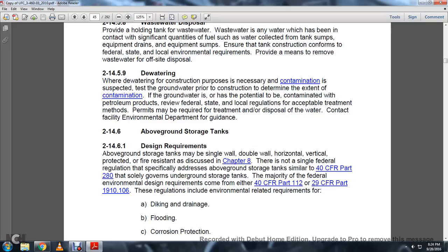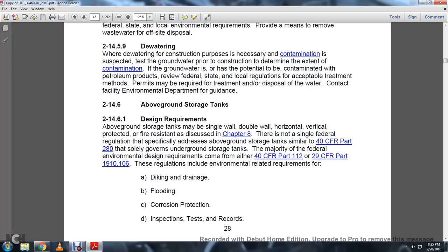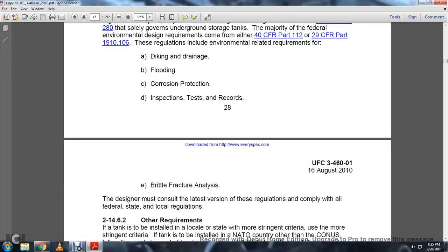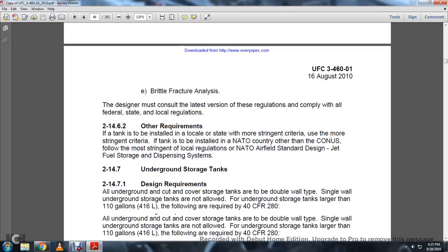The above ground storage tanks may be single wall, double wall, horizontal, vertical, protected with fire resistant as described in Chapter 8. There are no single federal regulations specifically addressing the above ground storage tanks, and similar to 40 CFR Part 280 that solely governs the underground storage tanks. The majority of the federal environmental guideline requirements come from either the Title 49 CFR, Title 40 CFR Part 112, the Title 29 CFR Part 1910 and 106. These regulations include environmental related requirements for diking, drainage, flooding, corrosion protection, inspection, detection, test records, brittle fracture analysis. The design must consult with the latest version of these regulations and comply with all the federal, state, and local regulations.